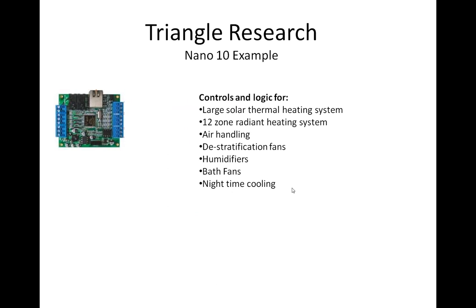Number one, this home is entirely heated with solar thermal through a 12-zone radiant heating system. It has a pretty complex heating sequence, which contains a lot of logic. It also has air handling, which moves hot air from certain parts of the house to colder parts. It also has de-stratification, which is taking hot air from high up on the ceilings and pushing it down lower.